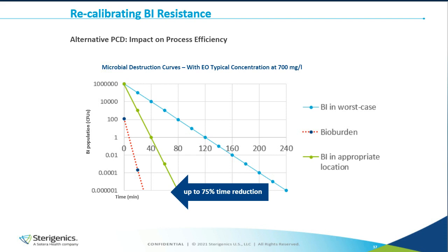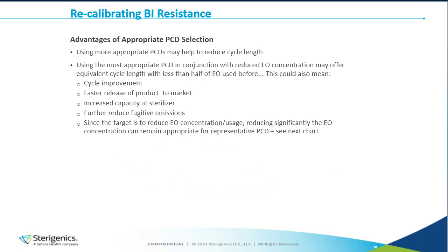Of course, the focus is not just on time, it is also on EO, so I'll come to that point a bit later. But the advantages of an appropriate PCD selection may help to reduce cycle duration. And if we reduce the cycle duration, we can increase the capacity of the sterilization modality. So it means that the shorter the cycle can be, the more cycles we can have as a throughput. So we can have, of course, less EO being used, and if we are reducing the amount of ethylene oxide in our cycle, naturally the residual level will also be lower. So it means that we could have a faster release time to market because the aeration time can be shortened as well. And definitely by reducing EO, we will reduce the fugitive emission coming out of the packaging and the products and the corrugated boxes.